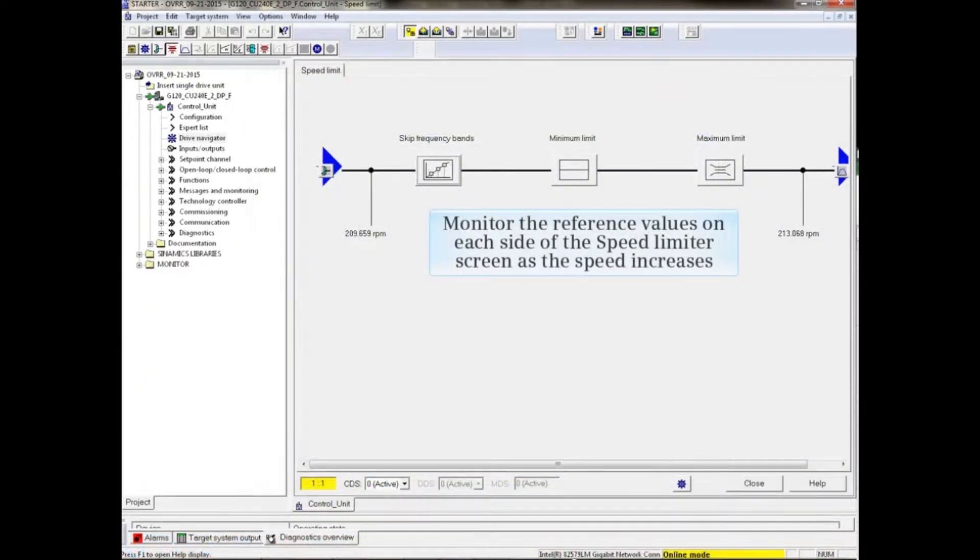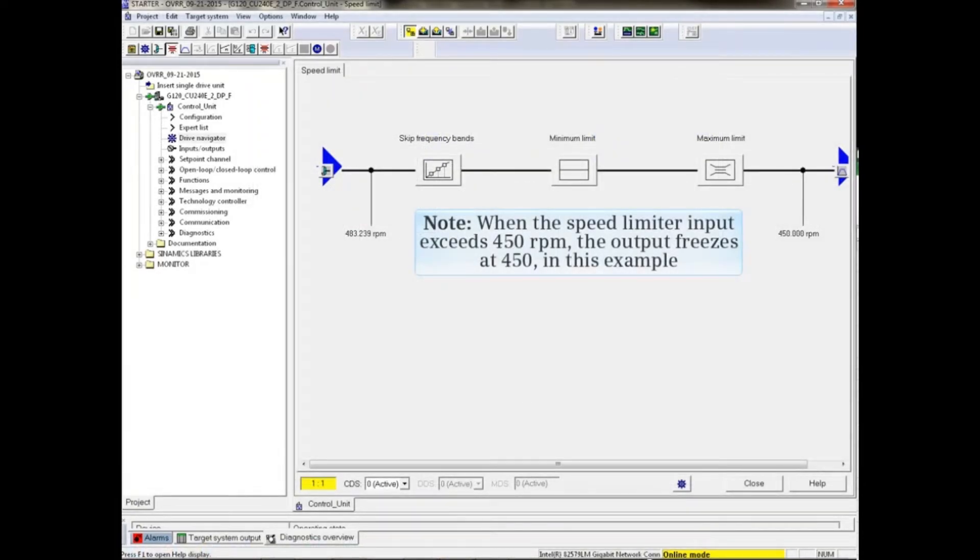Monitor the reference values on each side of the Speed Limiter screen as the speed increases. Note in the example that when the Speed Limiter input exceeds 450 RPM, the output freezes at 450.